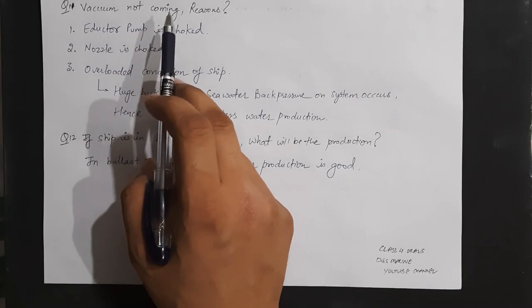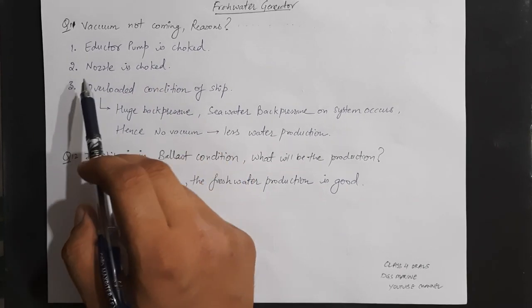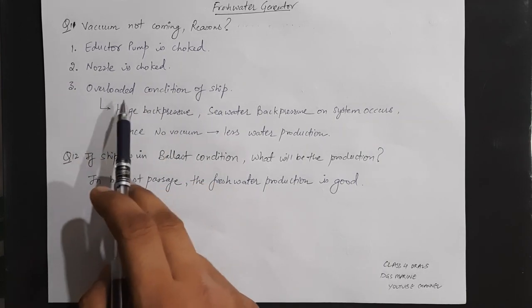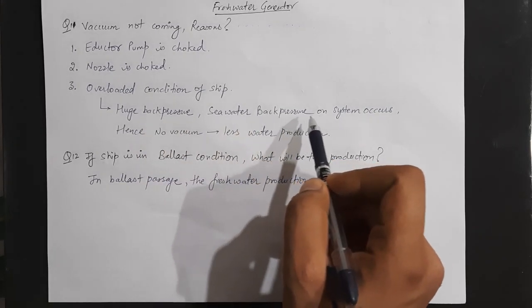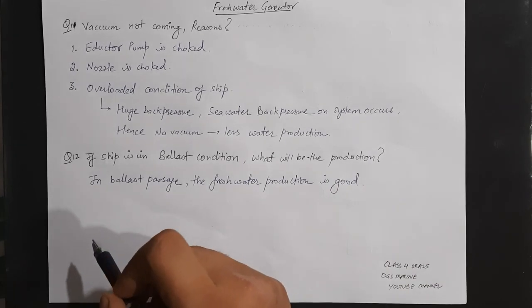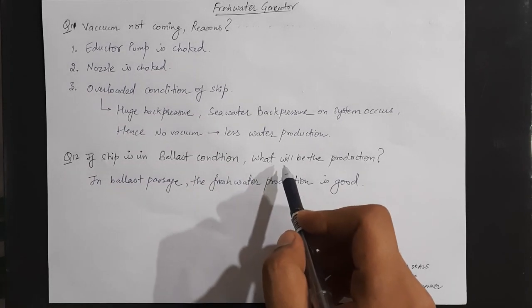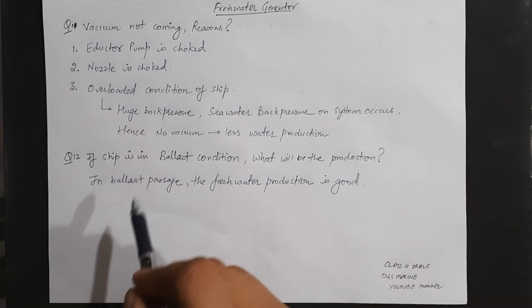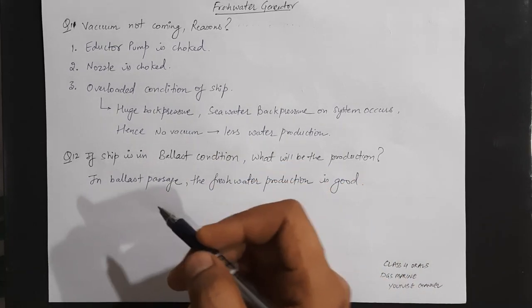Lastly, if the vacuum is not coming, the reasons are: first, the eductor pump is choked; second, the nozzle might be choked; third, the ship may be in an overloaded condition — in overloaded condition there is huge back pressure from seawater on the system, so not enough vacuum is produced and less fresh water is generated. Conversely, if the ship is in ballast condition, such as in tankers, fresh water production will be good because there is no huge back pressure, unlike the overloaded condition.